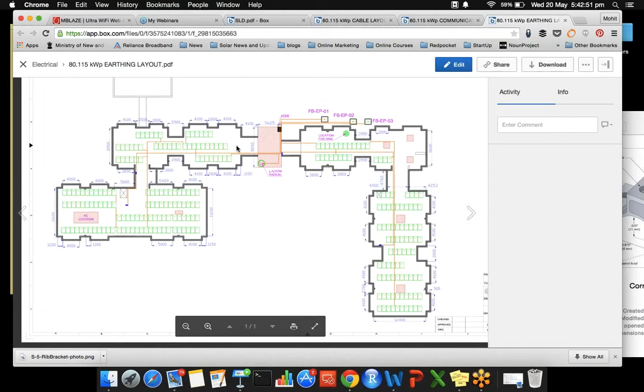The combiner boxes can be AC or DC or both depending on the project requirement. The DC combiner box is a device that combines the output of multiple strings of PV modules for connection to the inverter, while an AC combiner box is a device that can combine the outputs of multiple inverters and give a single output. We design combiner boxes which also provide the protection and performance monitoring for the photovoltaic system.